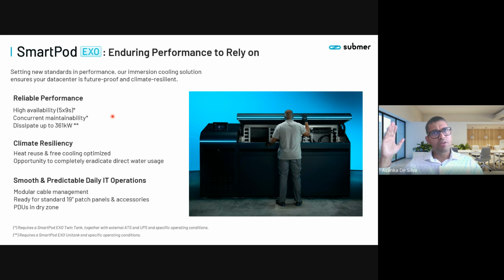It can go up to 361 kilowatts in one tank. It's got the five nines high availability, and it's really designed with ease of maintenance in mind. Okay, so you look at this, the front of the tank, you can remove the front panels and put your rack PDUs in there, so your bus bars can directly connect to the rack PDUs. The rear of the tank has quick connect piping, so it's easy to connect the water in and out.